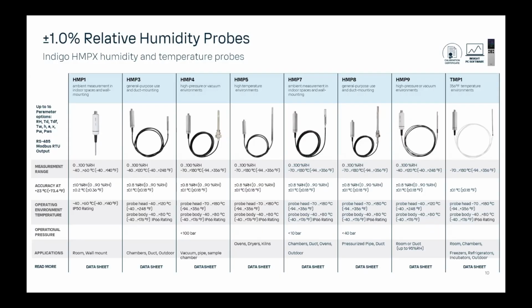And then the HMP8 is actually pretty unique because it offers an adjustable insertion depth. So it has a threaded fitting that slides along the length of the probe, and it also can be used with a ball valve kit. So that alone has a high pressure rating, not as high as the HMP4, but up to 40 bar, and then a high temperature rating up to 180 degrees Celsius. And then lastly, on the right, we have our smaller sensors. The HMP9 is designed with a very fast response time, and the TMP1 is temperature only.